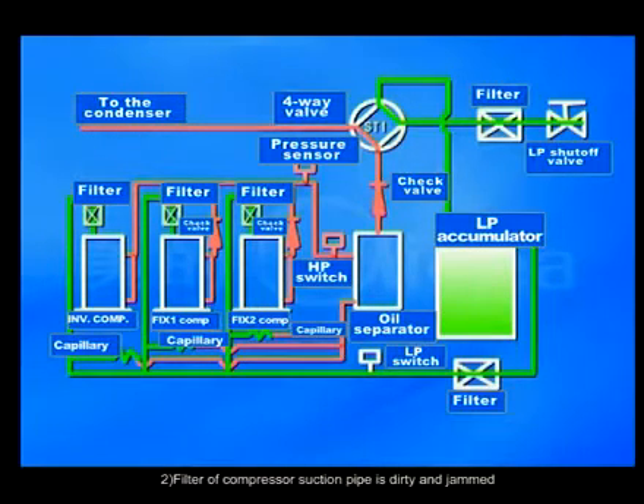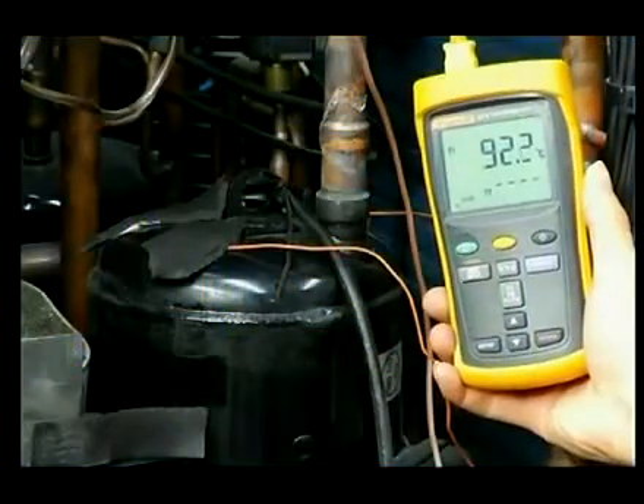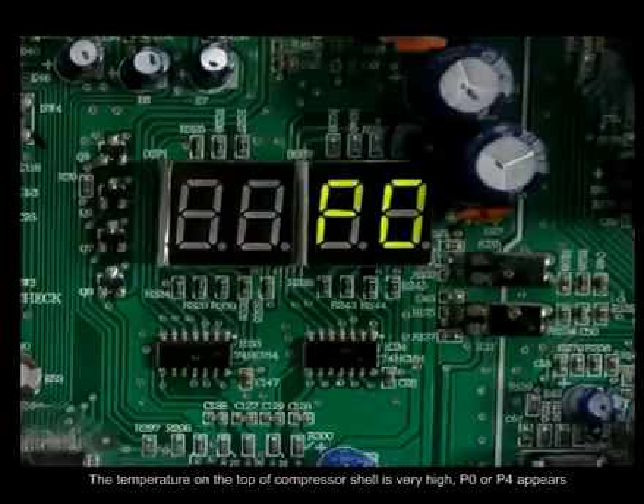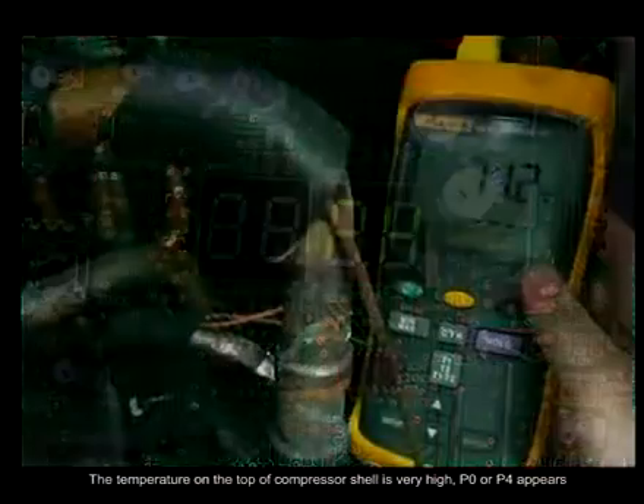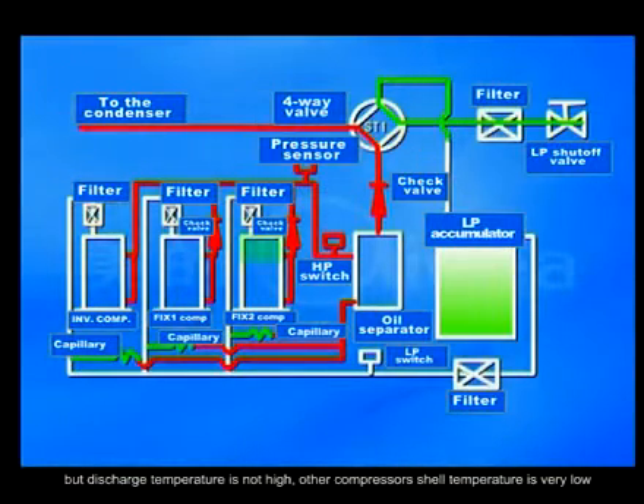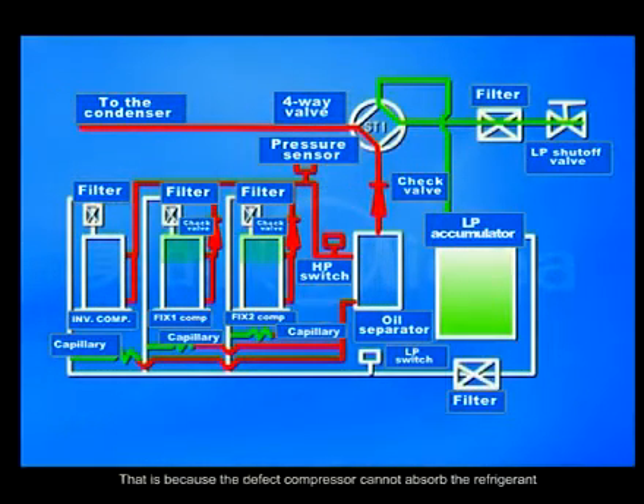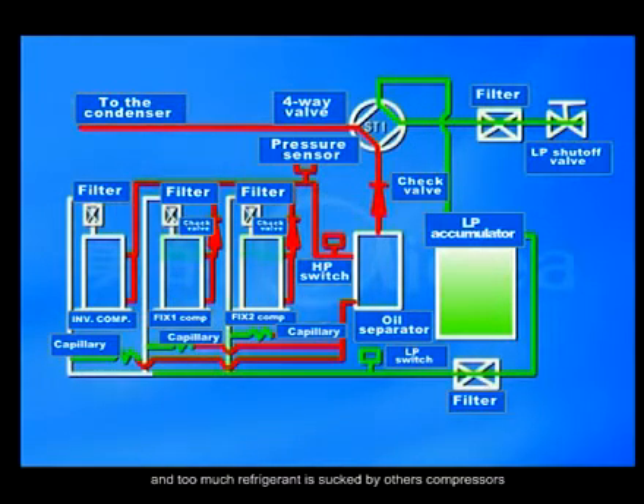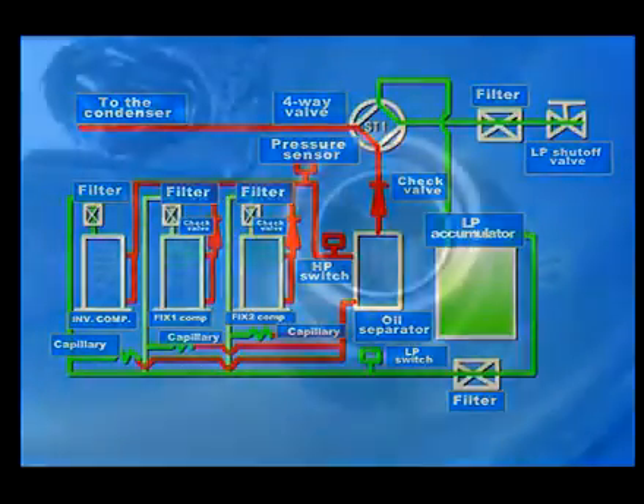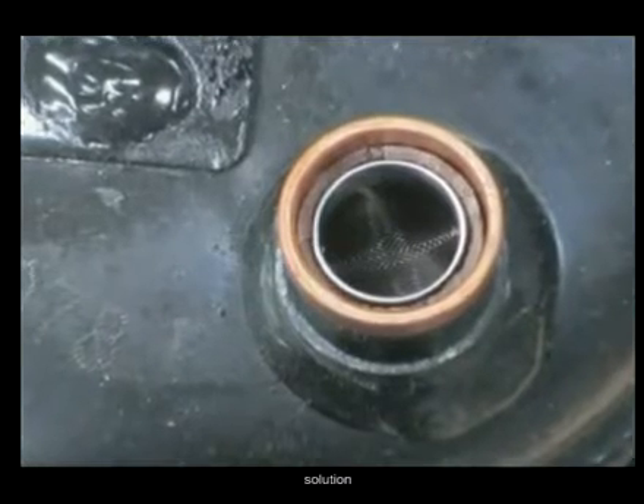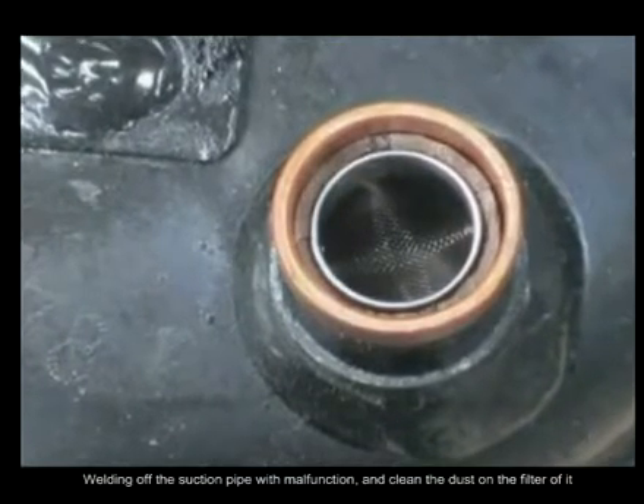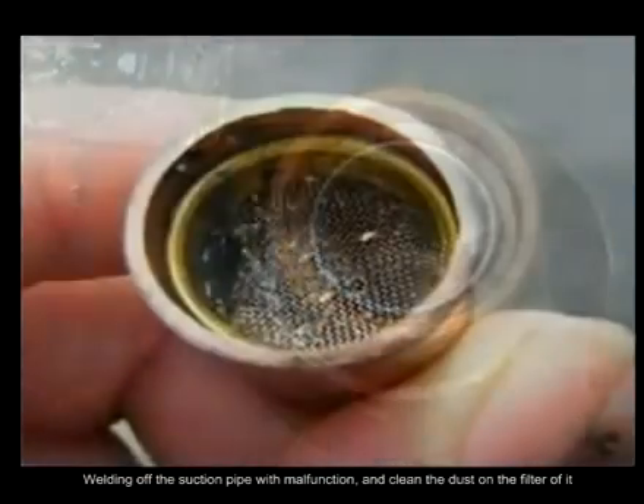2. The filter of the compressor suction pipe is dirty and jammed. The temperature on the top of the compressor shell is very high. P0 or P4 appears, but discharge temperature is not high. Other compressors' shell temperature is very low. That is because the defective compressor cannot absorb the refrigerant, and too much refrigerant is sucked by other compressors. Solution. Weld off the suction pipe with malfunction and clean the dust on the filter of it.